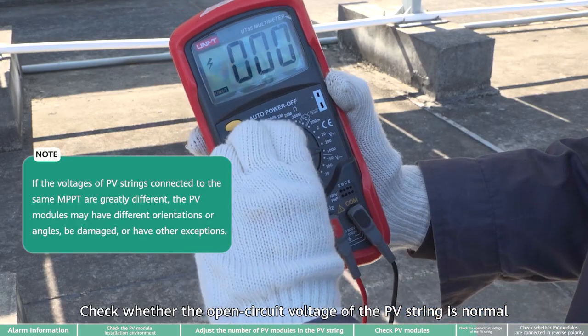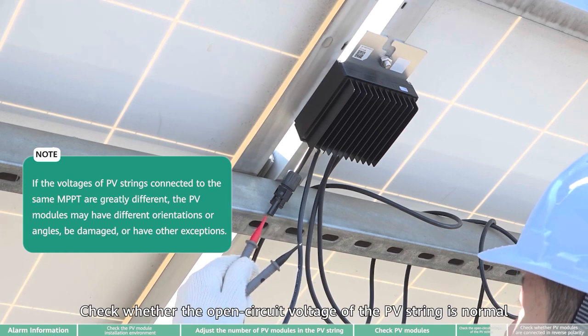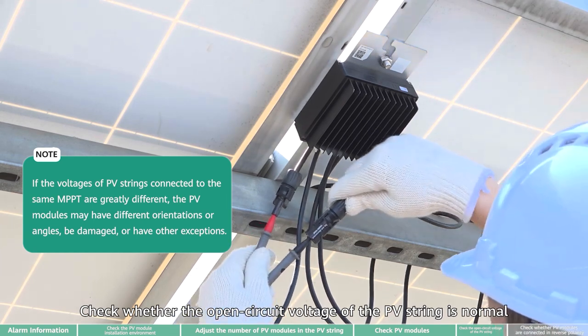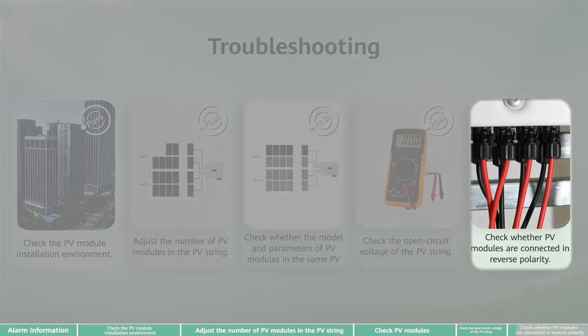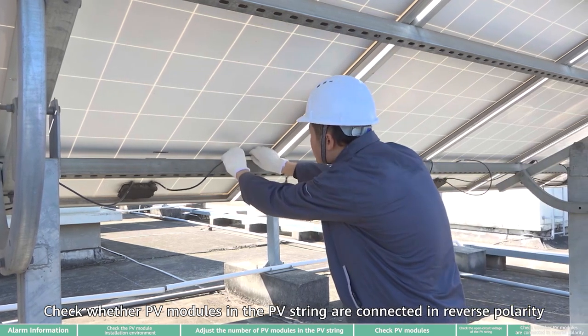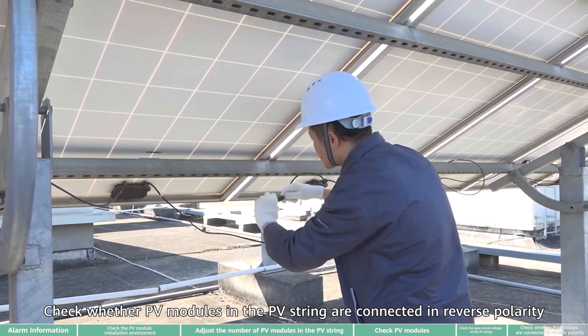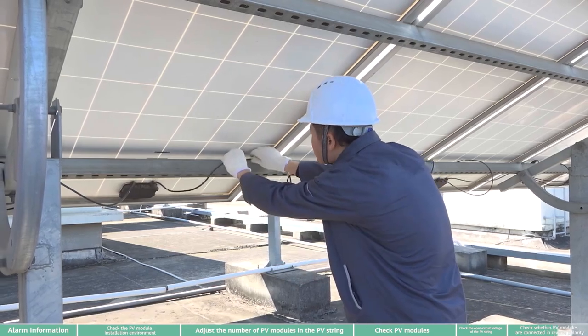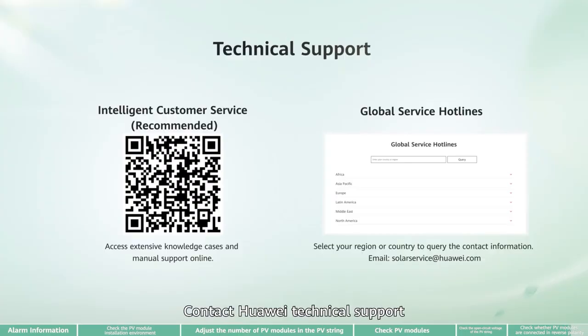Check whether the open circuit voltage of the PV string is normal. Check whether PV modules in the PV string are connected in reverse polarity. Contact Huawei technical support.